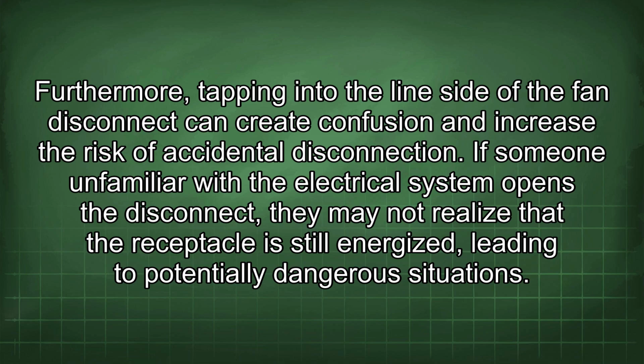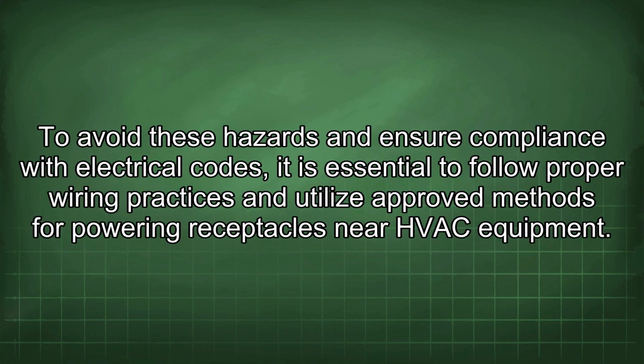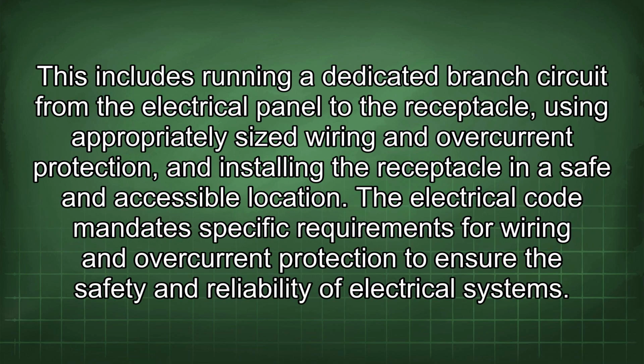If someone unfamiliar with the electrical system opens the disconnect, they may not realize that the receptacle is still energized, leading to potentially dangerous situations. To avoid these hazards and ensure compliance with electrical codes, it is essential to follow proper wiring practices and utilize approved methods for powering receptacles near HVAC equipment. This includes running a dedicated branch circuit from the electrical panel to the receptacle, using appropriately sized wiring and overcurrent protection, and installing the receptacle in a safe and accessible location.